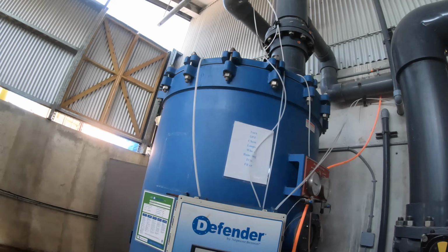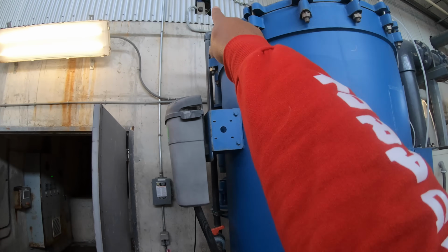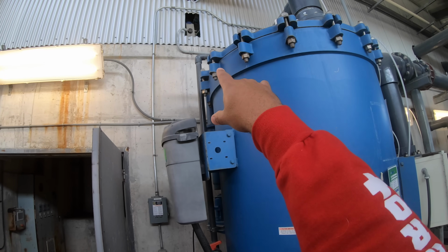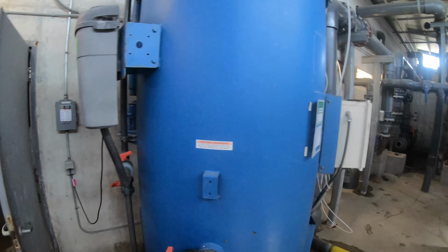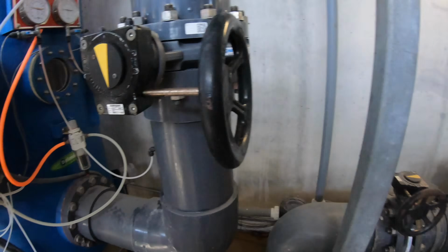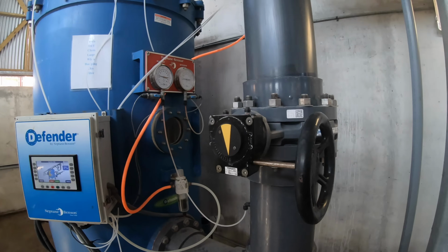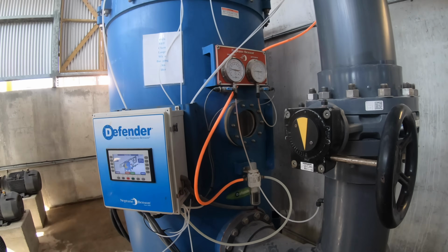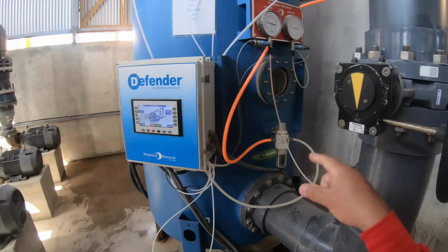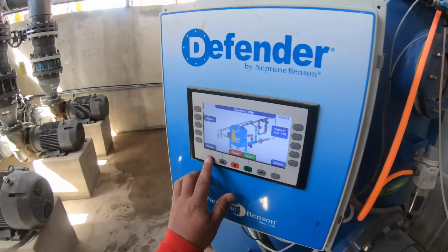You can't see it, right? You can't see it, no. But up there, well, maybe right there, hopefully, you'll see there's a valve there. And that valve is currently closed. That's returning to the pool. We don't want the water to return to the pool at this point, because we're in bump cycle. All this media is gonna be loose and fresh, and it actually goes through the tubes. And if we were to send the water back to the pool, it would actually dump the media in the filter all into the pool. We don't wanna do that, okay? So let's do a bump cycle.